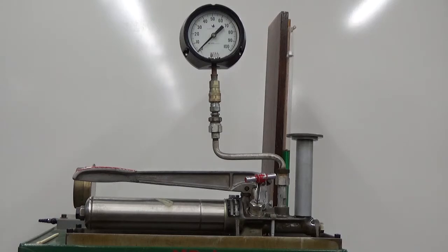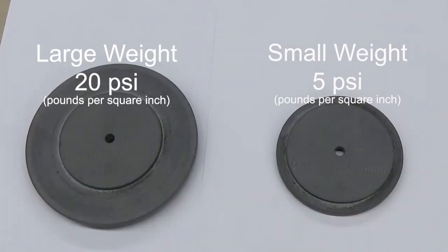In this video, we'll be demonstrating the use of a deadweight tester to calibrate a Bourdon pressure gauge. The deadweight tester consists of an oil-filled reservoir, a pressurizing pump, the test gauge, and the piston. The piston is where the calibration weights are placed to pressurize the system and calibrate the test gauge. In this experimental setup, we have two different sizes of test weights.